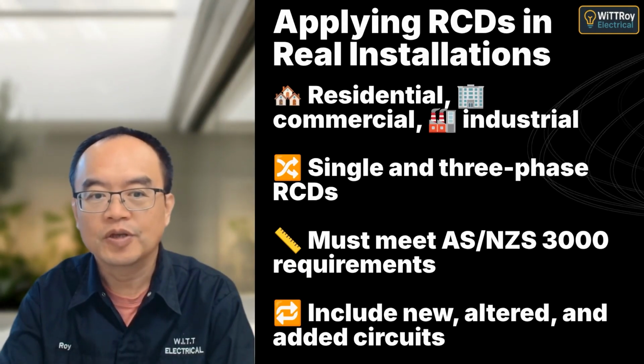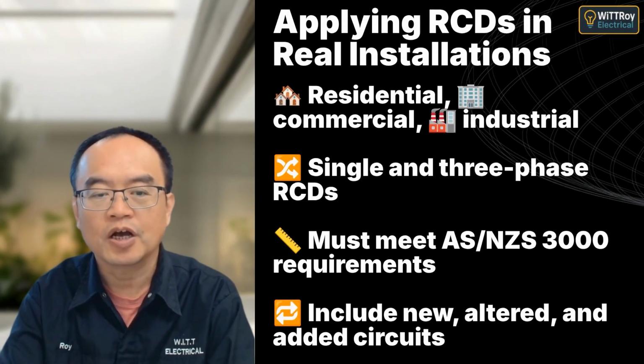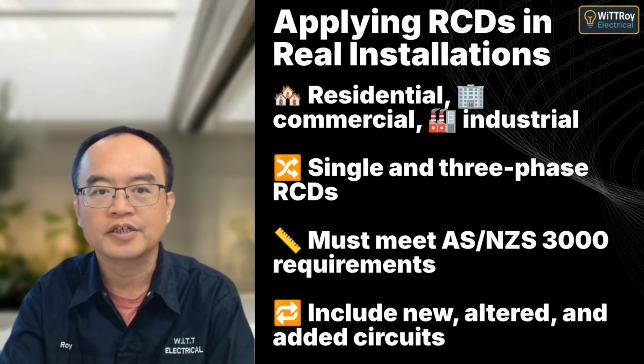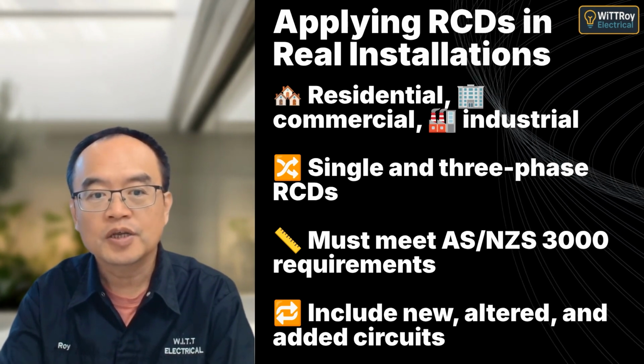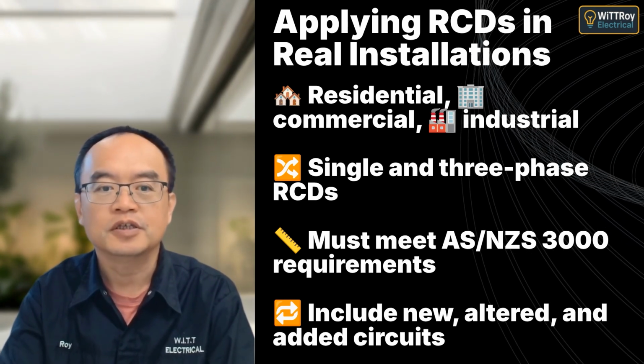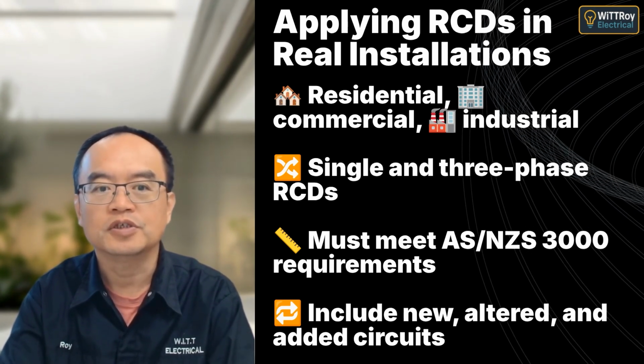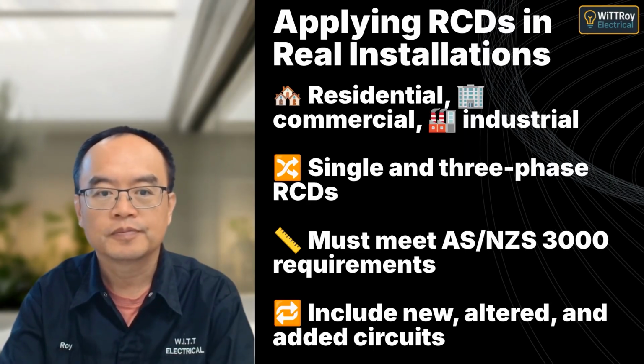Installation of RCDs varies across settings. Whether it's a home, office, or factory, the correct RCD type must be selected and placed according to AS/NZS 3000. This applies to new builds, additions, and retrofits. Nice work. That's 10.6.3 on RCDs. Let's now test your understanding with some Moodle questions covering types, tripping thresholds, and correct applications.